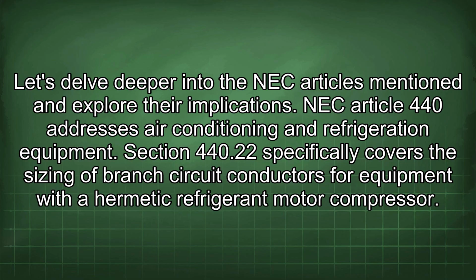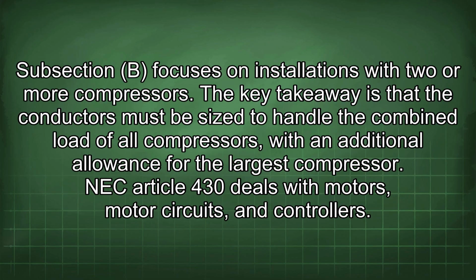Let's delve deeper into the NEC articles mentioned and explore their implications. NEC Article 440 addresses air conditioning and refrigeration equipment. Section 440.22 specifically covers the sizing of branch circuit conductors for equipment with a hermetic refrigerant motor compressor. Subsection B focuses on installations with 2 or more compressors. The key takeaway is that the conductors must be sized to handle the combined load of all compressors, with an additional allowance for the largest compressor.